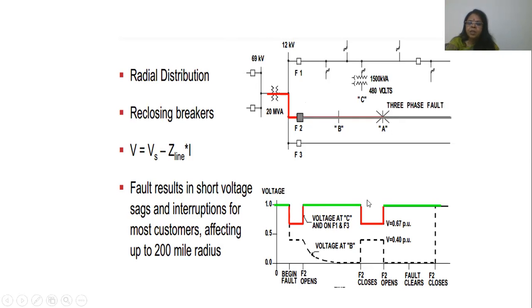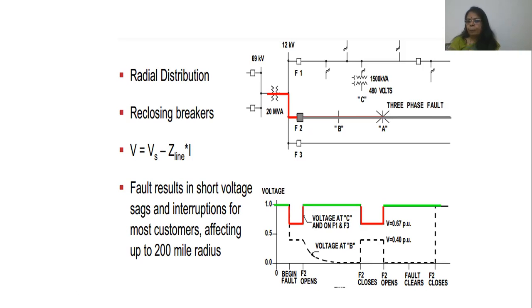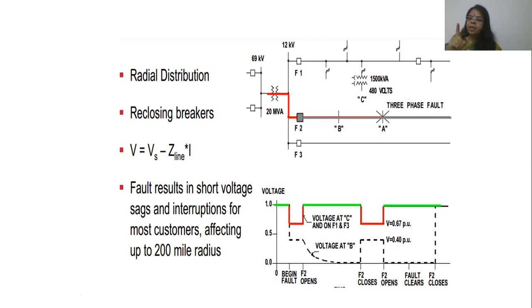The relay will energize the F2 breaker, causing it to open — F2 voltage becomes zero since it is disconnected. Since the fault is isolated, F1 and F3 voltages quickly recover. However, both F1 and F3 experienced the sag even though the fault was only in F2.